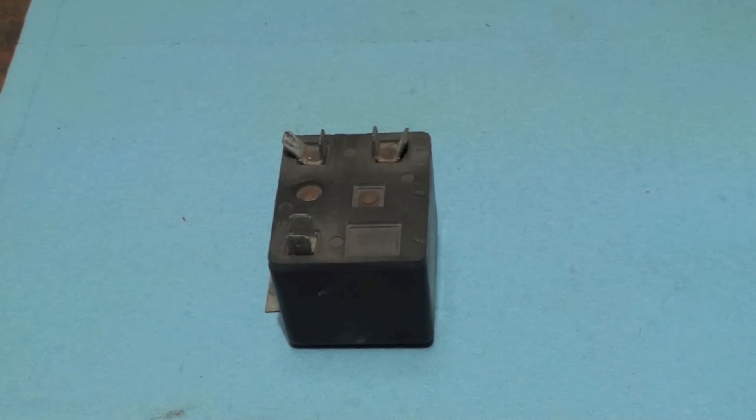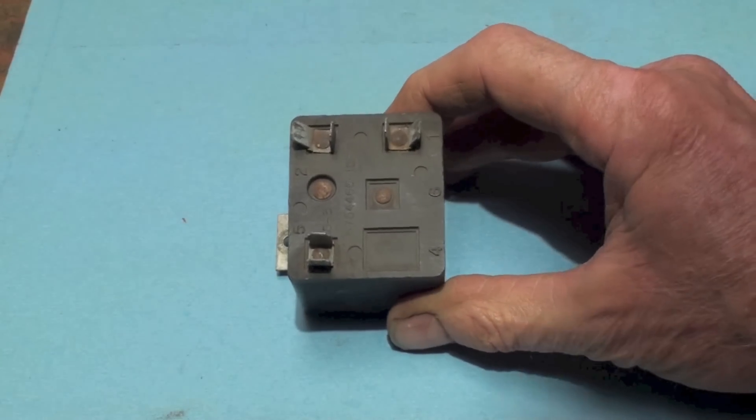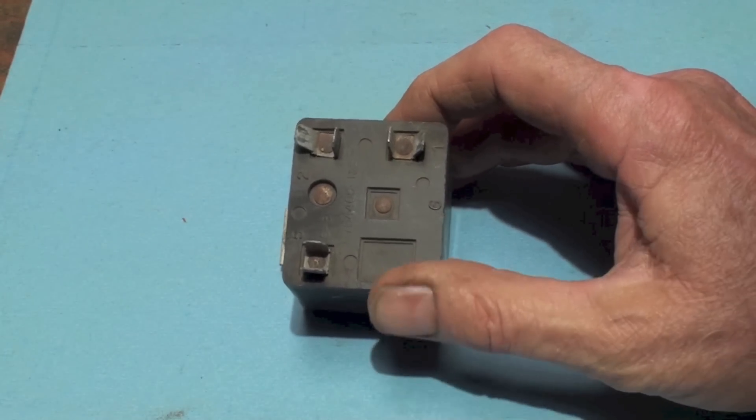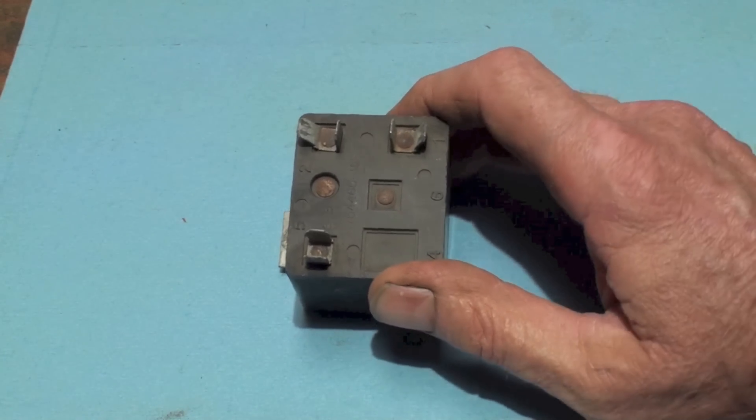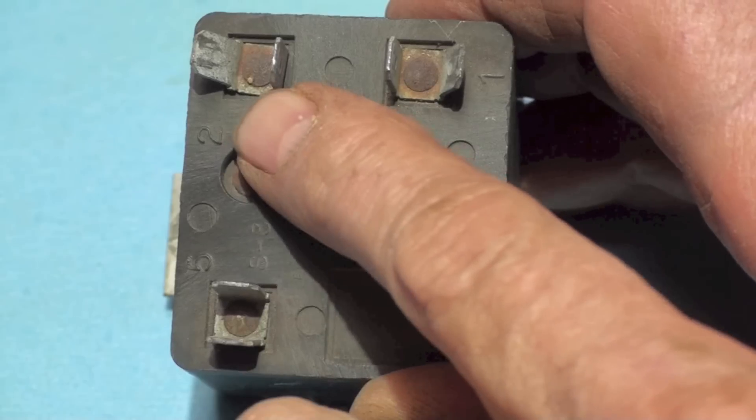The potential relay is a very common relay used in hard start compressors for refrigeration and air conditioning. It has three usable terminals on it. If you look at this one, it's got a five right there, it's got a two right there, and it's got a one.